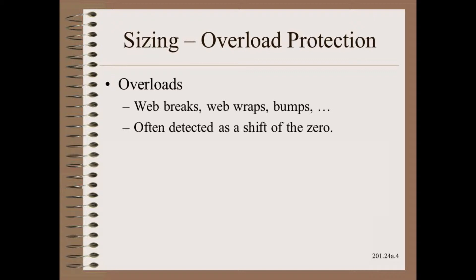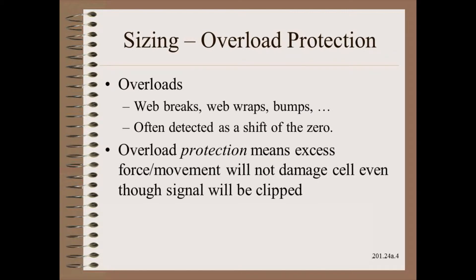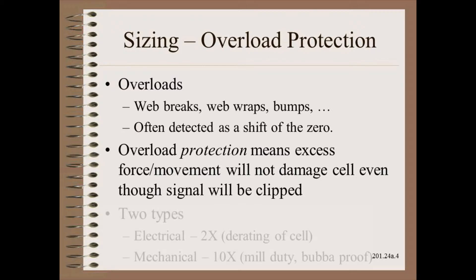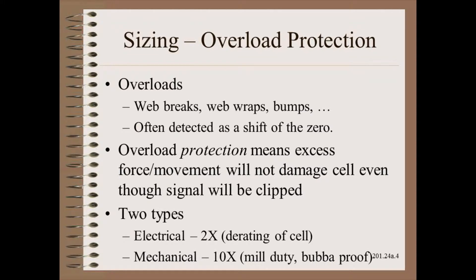Overloads are a regular part of the real world. You don't want to have these events damage the cell so that it needs to be re-zeroed or worse yet replaced. These events can come from any number of different sources such as web breaks, web wraps, and something bumping or even just tapping the load cell roller. Overload protection means that the cell will not be damaged even though momentarily the signal will be clipped and thus unusable. We could just increase the size of the load cell to accommodate overloads — this is in effect what electrical overload protection does.